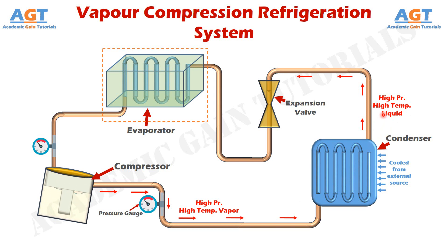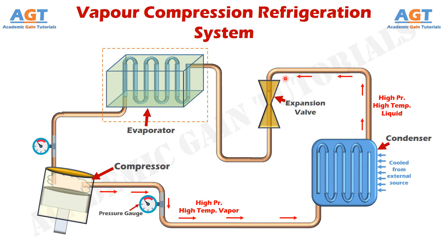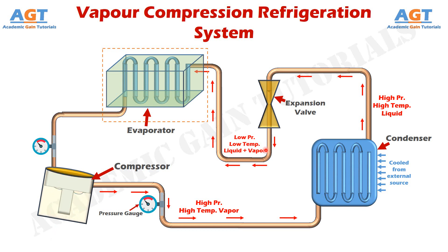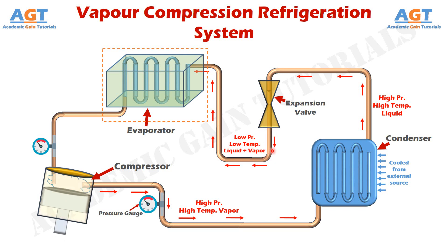This high pressure, high temperature liquid refrigerant leaves the condenser and passes through the expansion valve or throttle valve. The high pressure liquid refrigerant coming from the condenser is expanded inside this expansion valve. When expansion occurs, the pressure between the molecules decreases considerably, and thus the temperature falls. So, this high pressure liquid refrigerant is expanded into low pressure, low temperature liquid refrigerant. In practical use, we actually obtain a mixture of low pressure, low temperature liquid and vapor refrigerant — a very cold, chilled mixture coming out of the expansion valve.